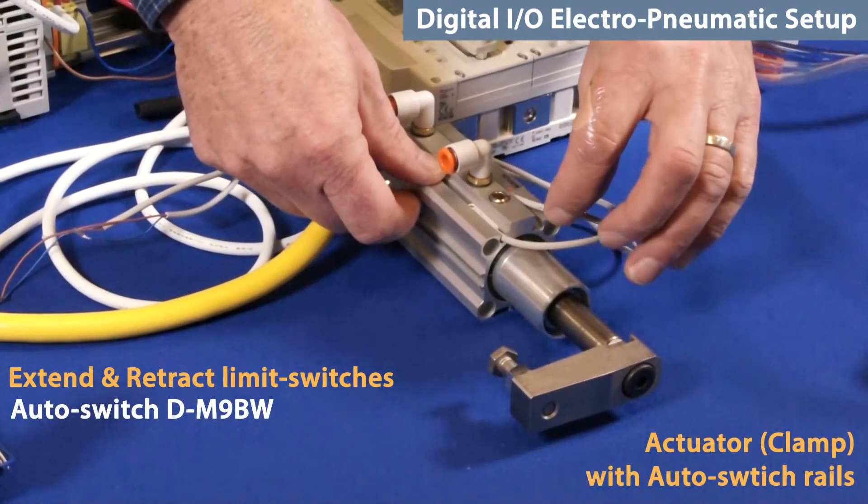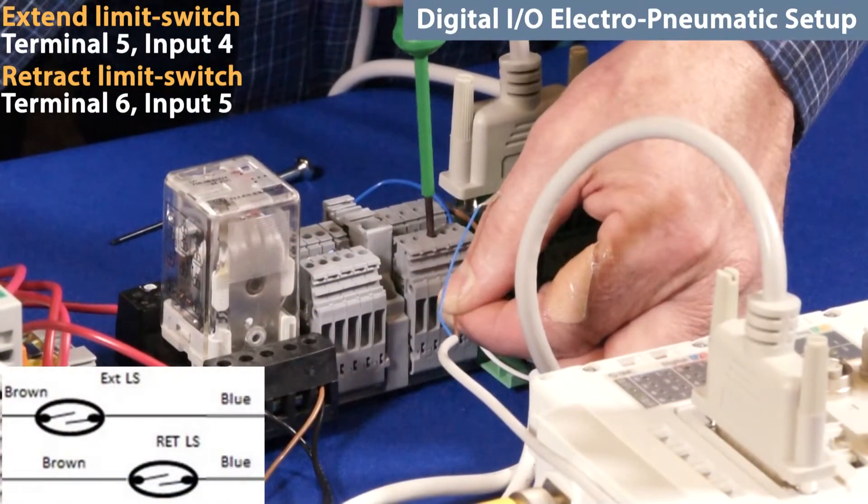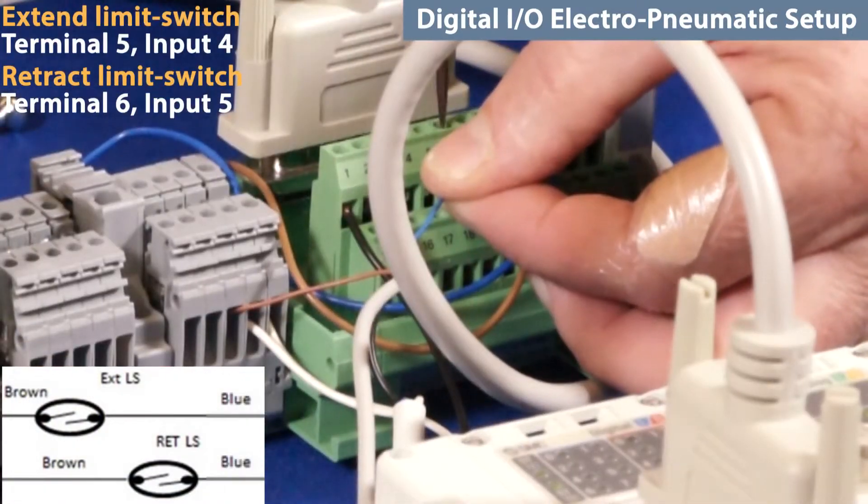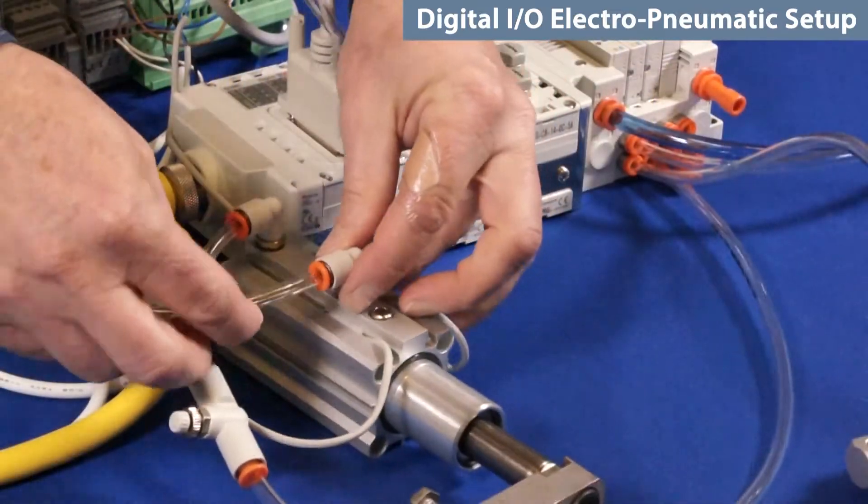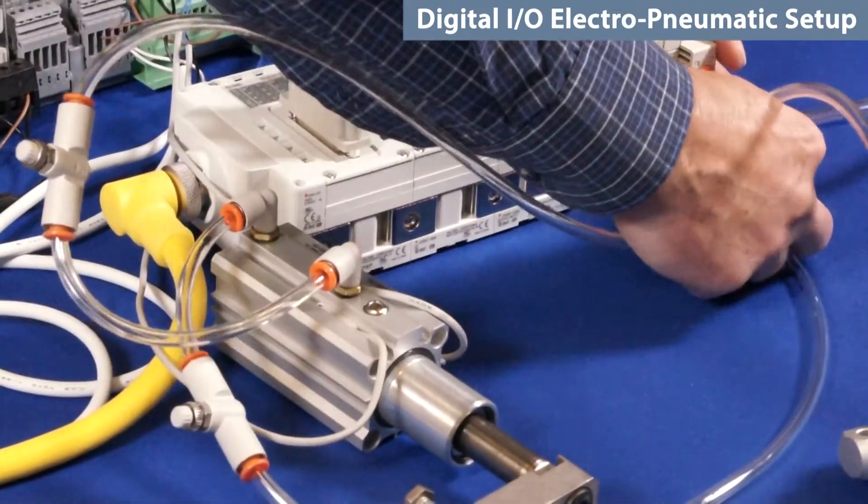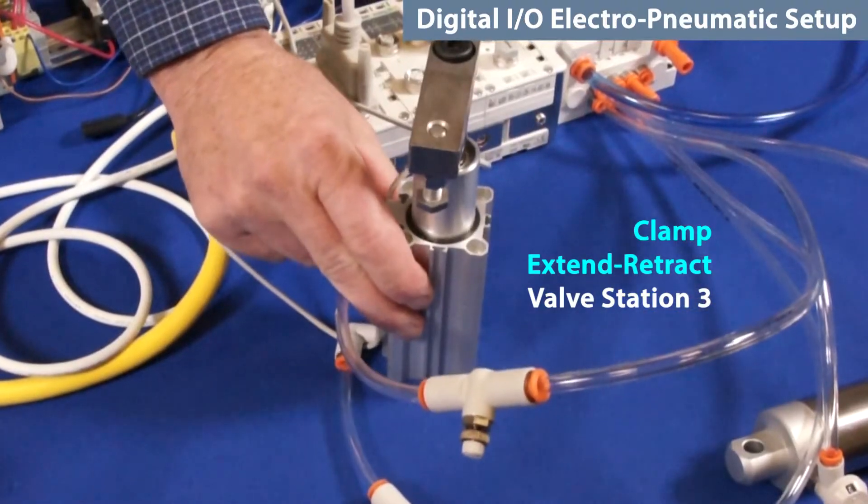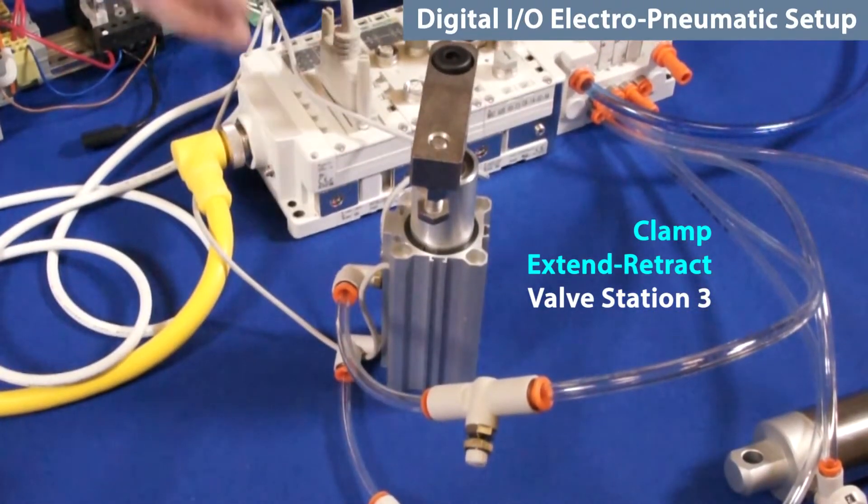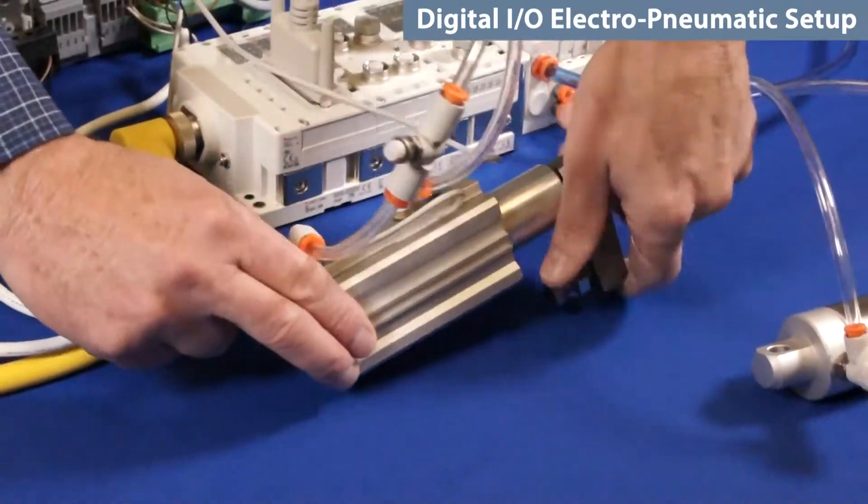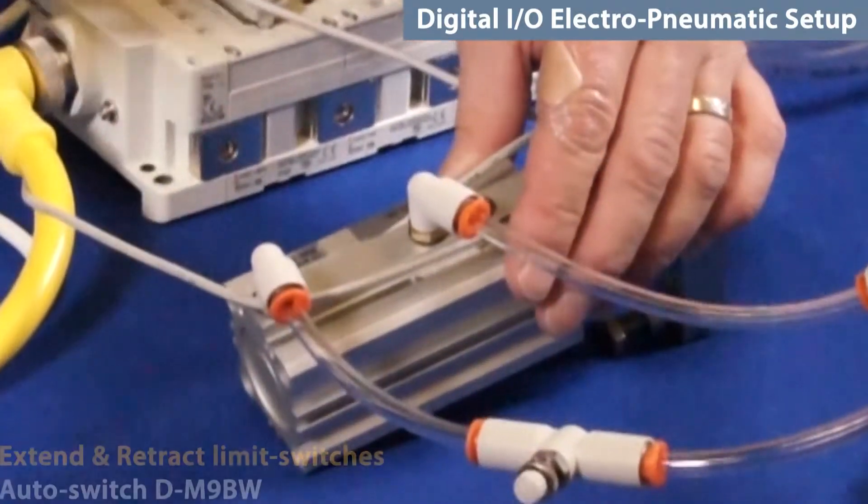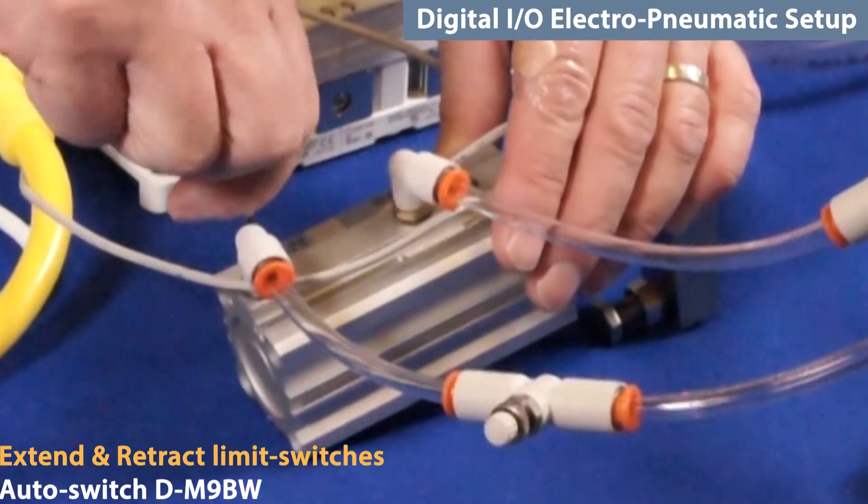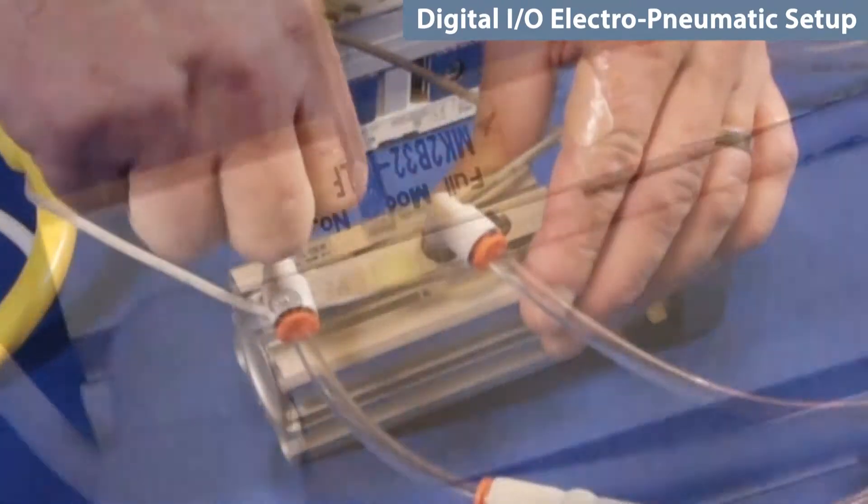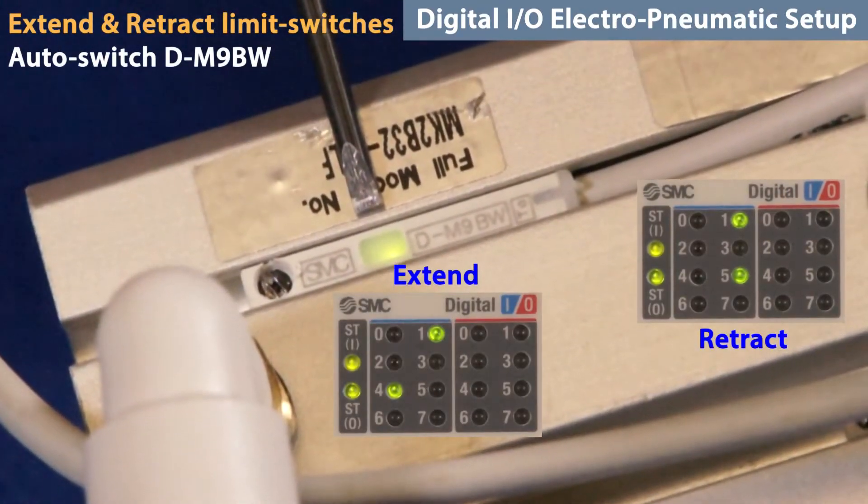Now, to receive signals from the cylinder's auto-switches, we connect them to 24 volts and to inputs 4 and 5. With air off, hook up the tubing from a valve to the actuator we want to monitor. Turn air on and verify pneumatically by using the manual overrides. To adjust the auto-switches, slide them into the actuator grooves and move them until the light turns on when the cylinder is in the proper position. Verify connection with the Digital I/O module lights.